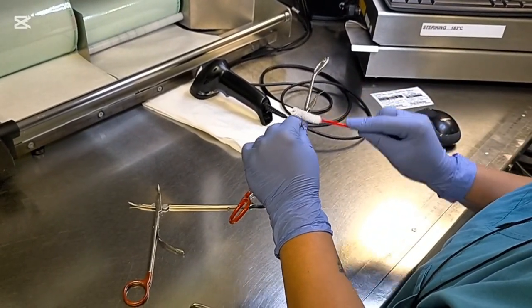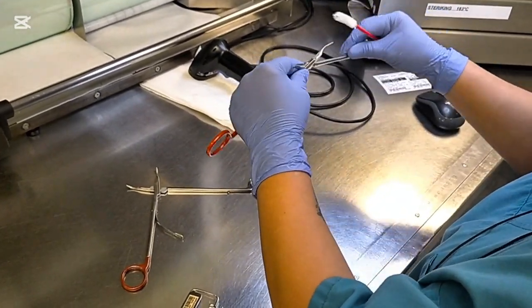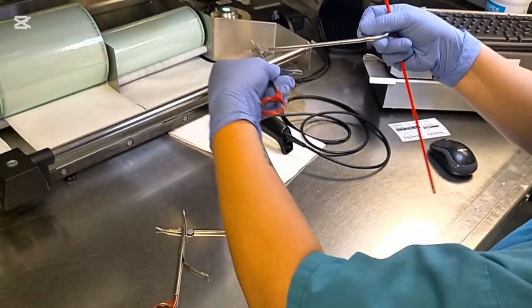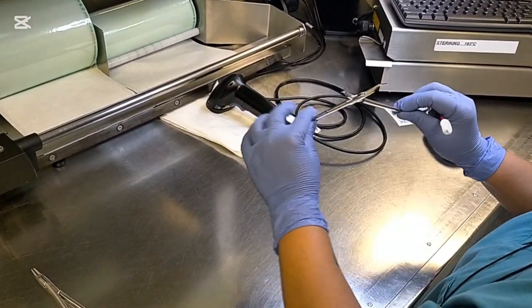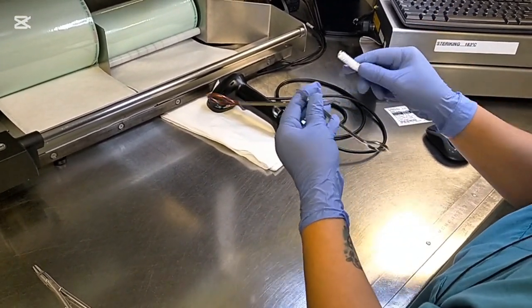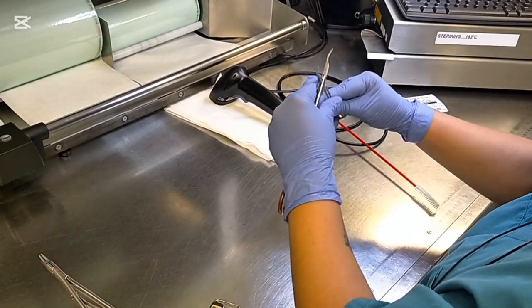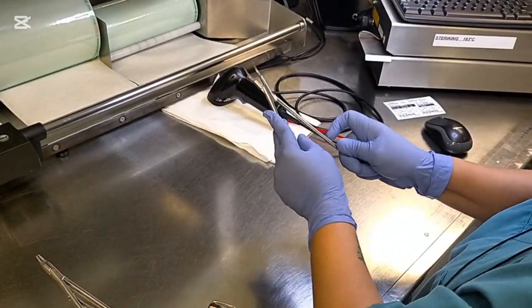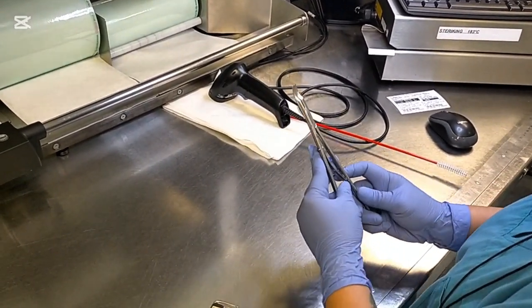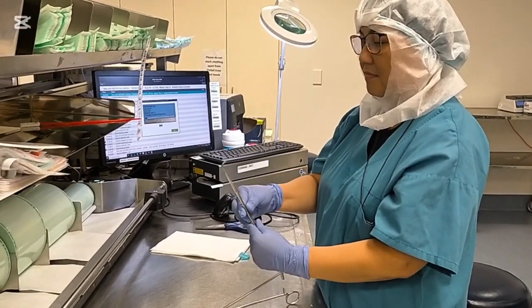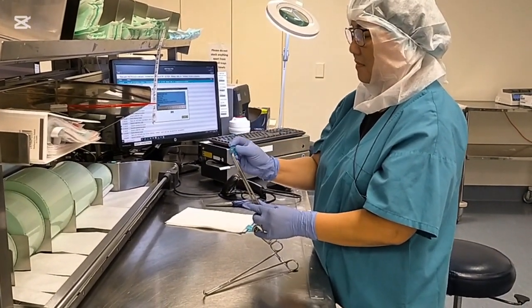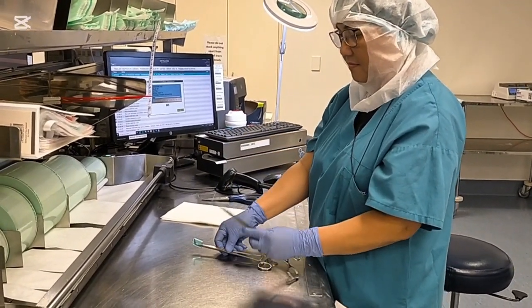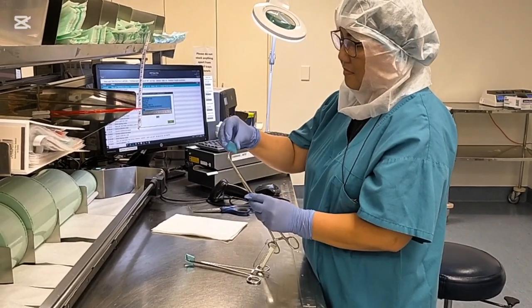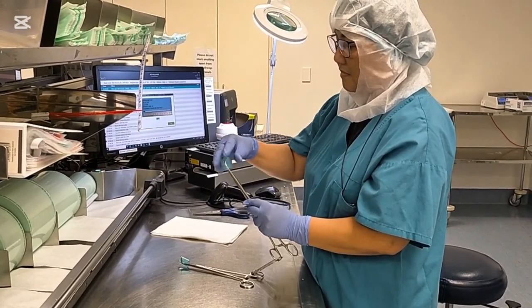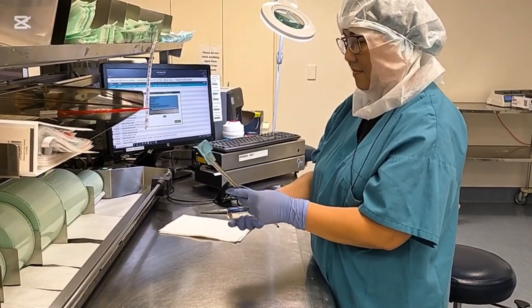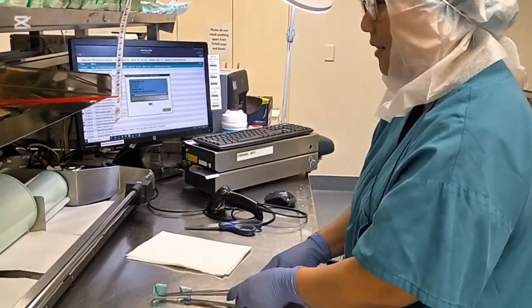Before we pouch, we have to inspect our device, its cleanliness and functionality, making sure that there's no dry blood, small bones, or any other dirt. It should be 100% clean and functional. If everything is okay, then we will proceed. Another thing to note is the tip protector. If the instrument is sharp, it may damage the pouch, thus compromising the sterility of the device. So, it is advisable to use tip protector to prevent damage to the pouch, and this is how we do it.